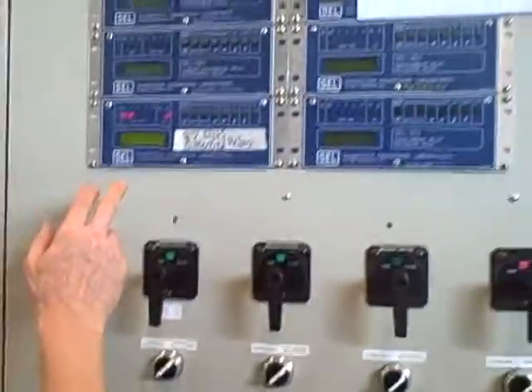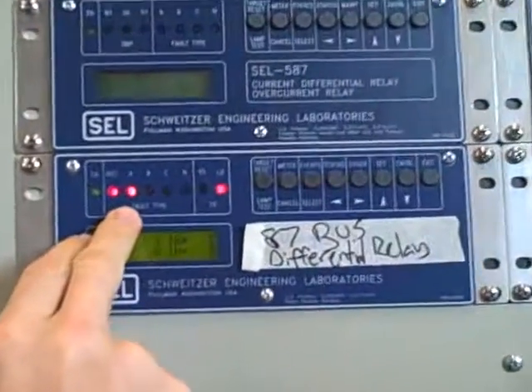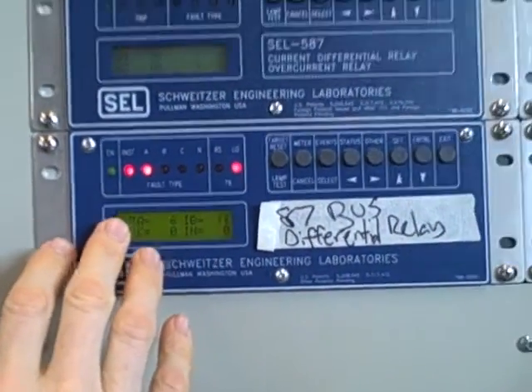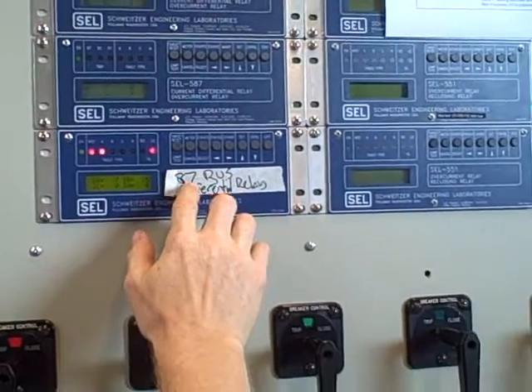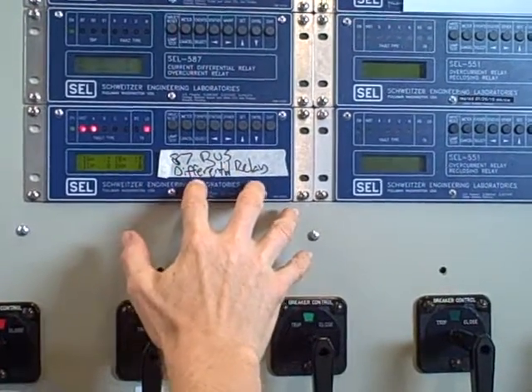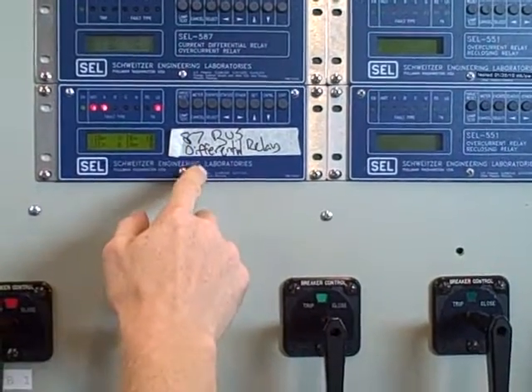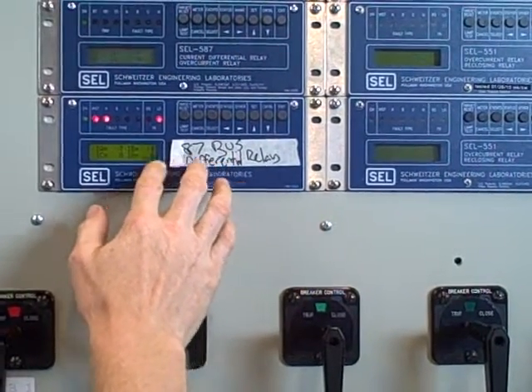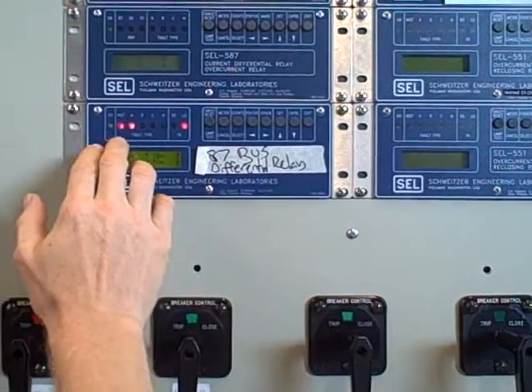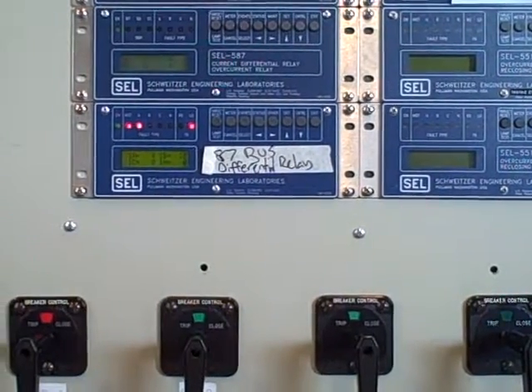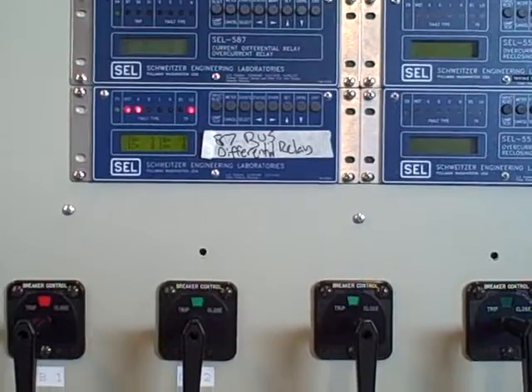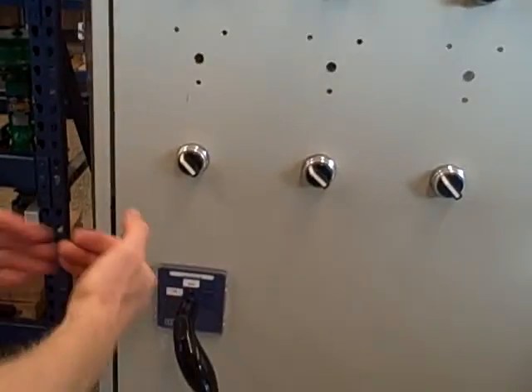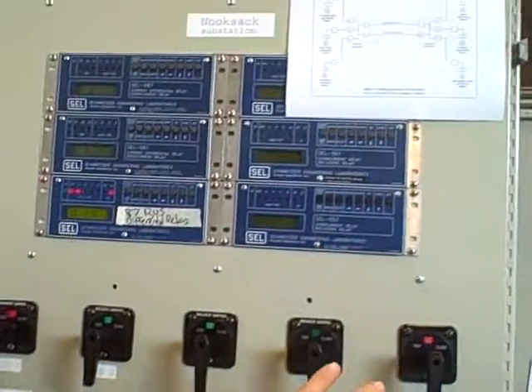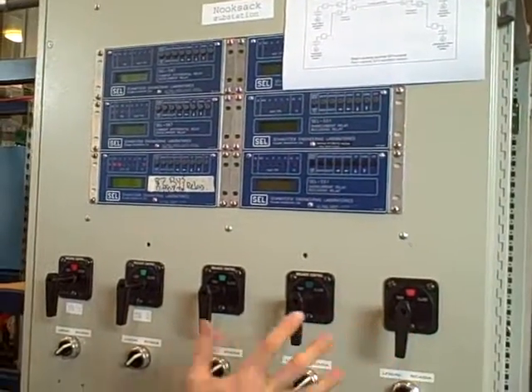And there we go. So we come over here, and sure enough, I have an instantaneous trip on A phase. Again, the instantaneous part makes more sense when you realize this is a 551 relay. It's really an overcurrent relay that we have adapted to be an 87 differential. So we've adapted it to work as an instantaneous current trip, and it saw the difference on A phase and said, okay, we've got ourselves a current difference problem. And so it tripped the 87 lockout relay, and the bank of switches on the 87 lockout tripped all 5 breakers on the bus, and that isolated the bus from what it thought was a fault.